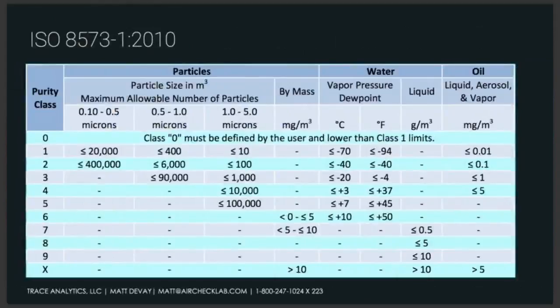So here's a pretty intimidating chart. This is the class chart for ISO 8573. This kind of outlines, if you pick and choose classes to build your system around, these are the limits for those classes. So if you look across the top, you've got particles, water, and oil. Across the side, you've got the purity class itself, and then in the cells where the columns and the rows meet, those are the limits that you have to achieve if you want to say your system is meeting a particular class. You have no obligation to say, okay, well, I want a class 2 for particles. That doesn't mean you also need class 2 for water and oil. So you can pick and choose by section which classes you want.